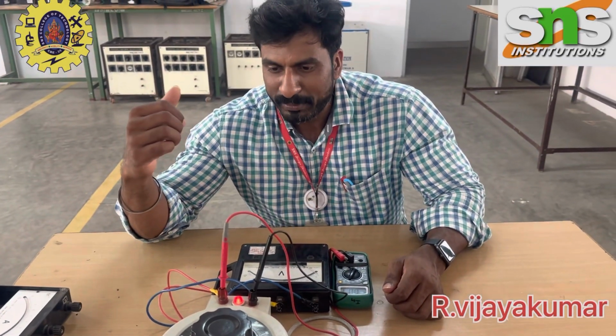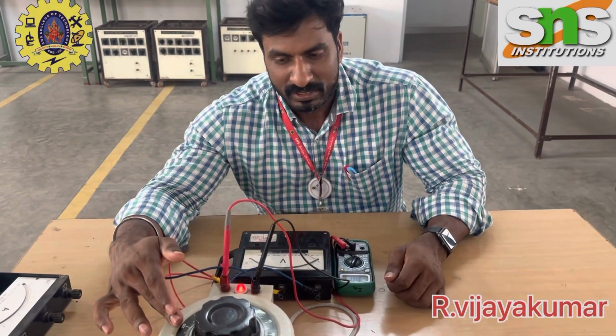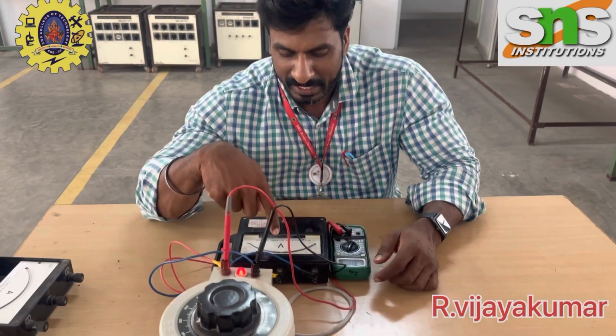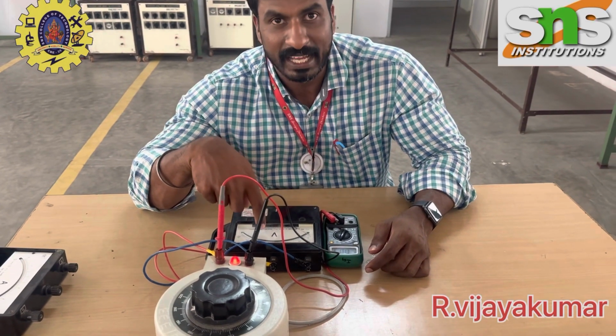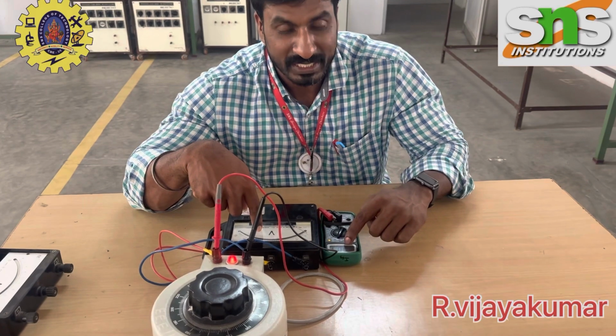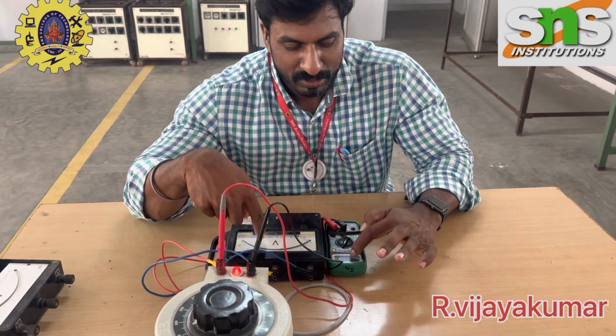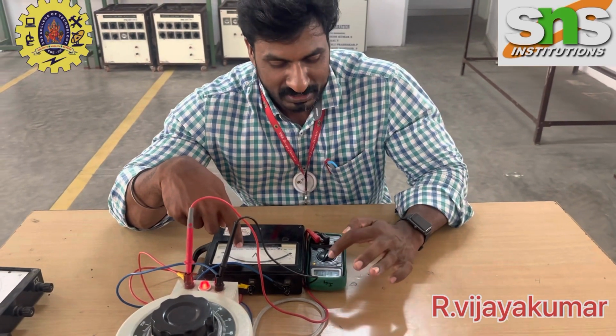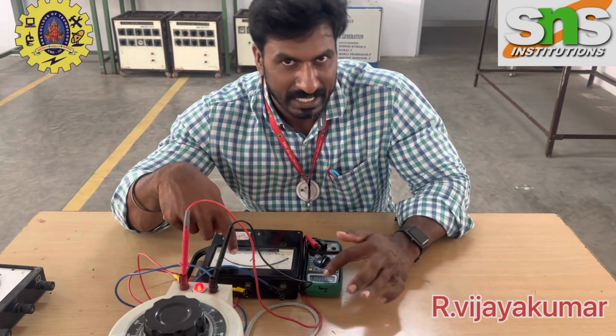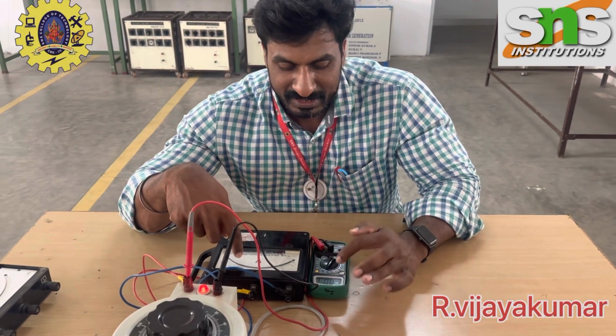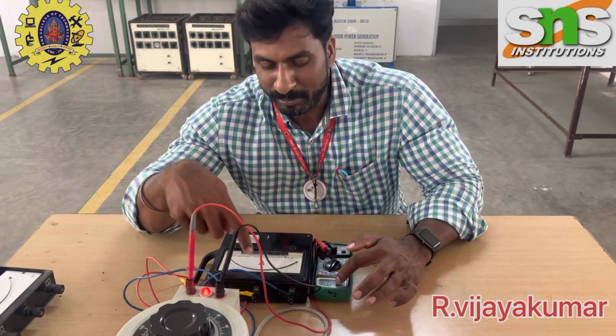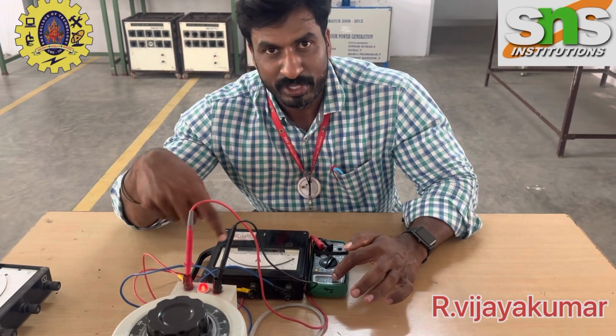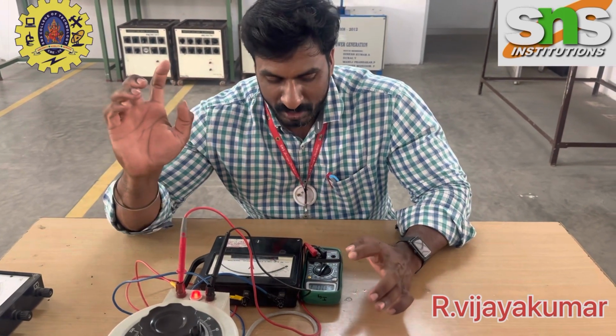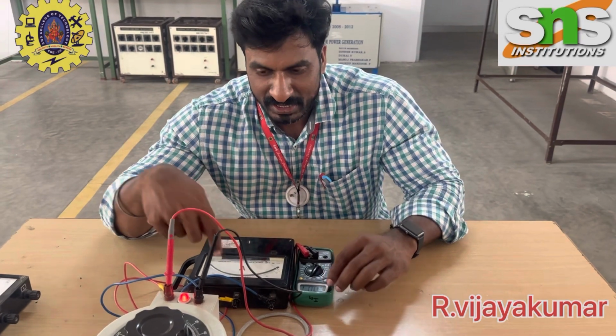For this experiment I am using a single phase auto transformer and calibrating the meter. This is the error meter, and now I am using a digital voltmeter, which has no error since it is new and already calibrated. I am connecting this digital voltmeter in parallel with the meter I am going to calibrate. Now both meters show zero voltage.